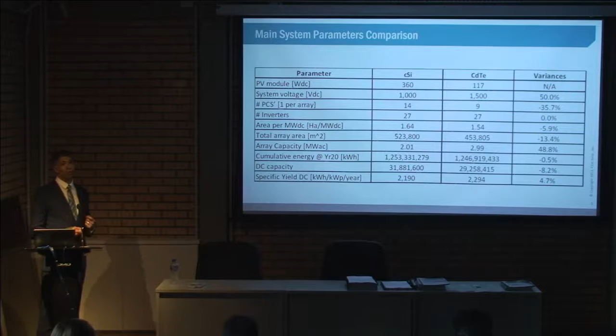Another important parameter is this one here, and this has to do with the inverter rating. Something that we are noticing here in Brazil and in other countries in Latin America is that both developers and consultants, when they are running PVsyst, are using the nominal rating of the inverters. So they are not adjusting the capacity of the inverters for elevation and temperature. That could lead to shortfalls during project implementation if it is not corrected. In other words, the energy simulations done with the nominal rating will not provide accurate, representative results.